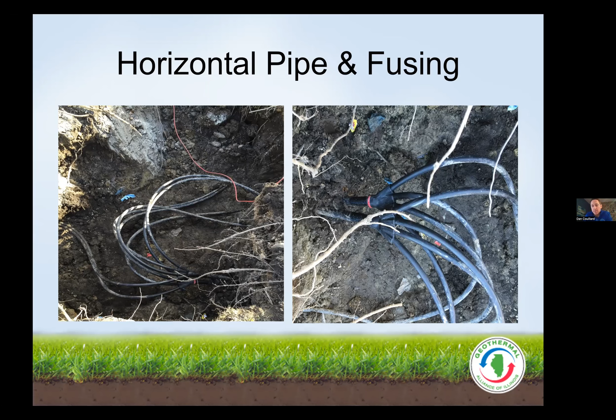At this point you have an entire completed outdoor geothermal system put together. They come back inside and attach a flush cart to the header pipes to flush out all the air and any dirt that got into the pipes during installation. Then they pressure test it, to make sure there's no leaks, double checking all their fuses.